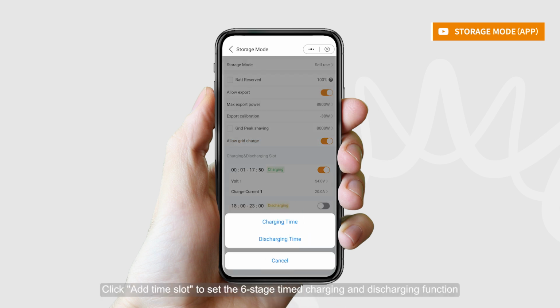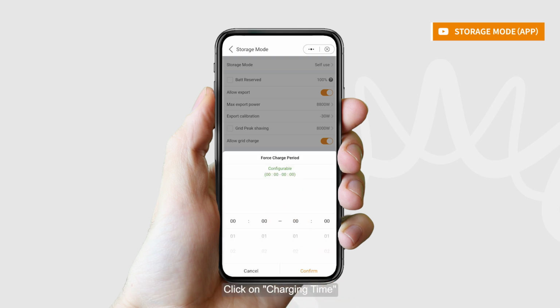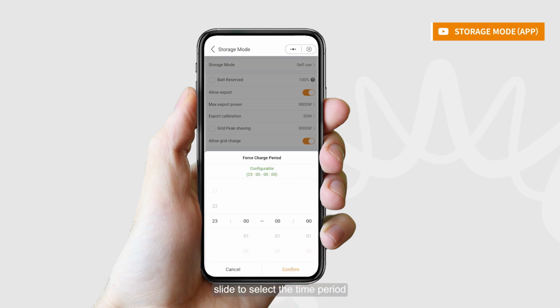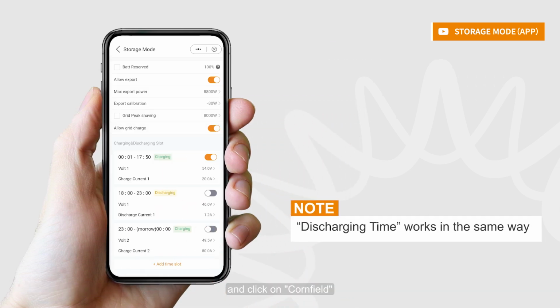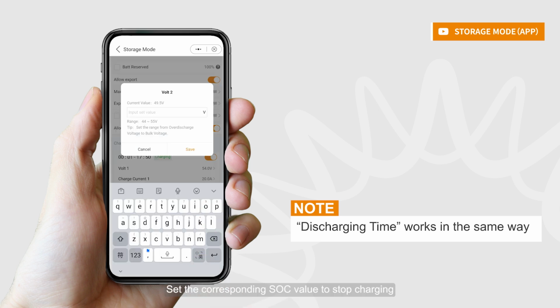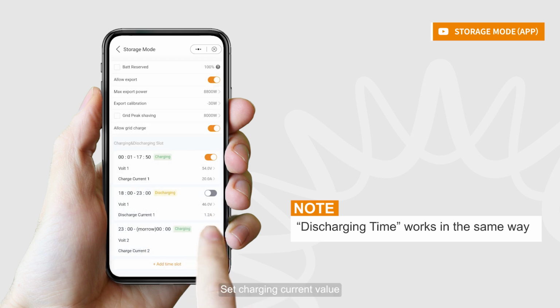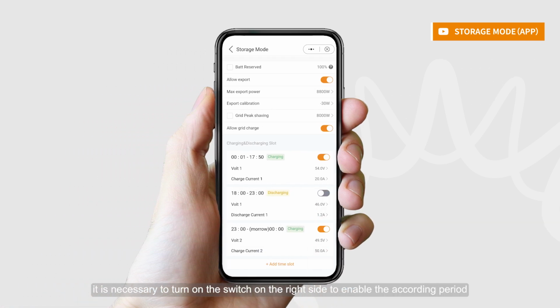Click Add Time Slot to set the 6 periods of timing charging and discharging. Click on Charging Time, slide to select the time period, and click on Confirm. Set the corresponding SOC value to stop charging. Set charging current value. After setting the parameters, it is necessary to turn on the switch on the right side to enable the according period.